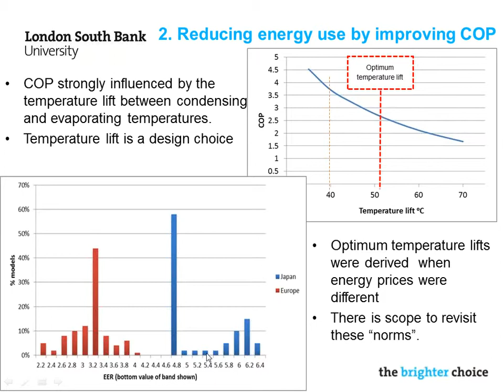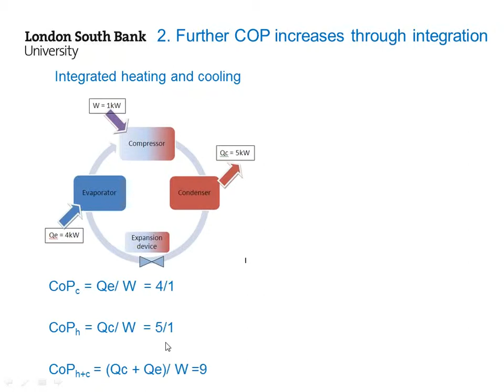This is a diagram showing the components of a refrigeration system—evaporator, compressor, condenser, expansion device—and shows some typical heat and energies going in. COP in cooling load is the cooling capacity, 4, divided by the compressor input, 1, so it's 4. In heating mode, 5 divided by 1. In cooling and heating mode combined, we can get 9. We need to work on how to achieve those sorts of COPs.